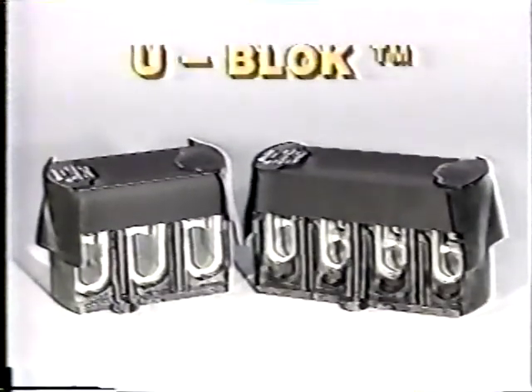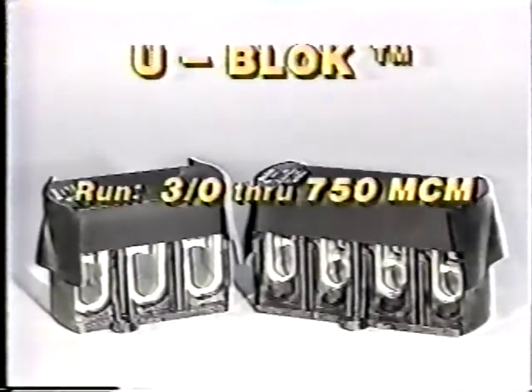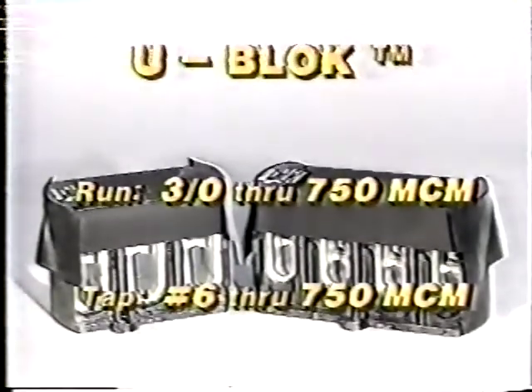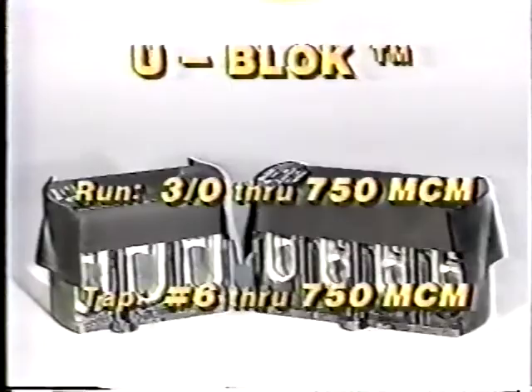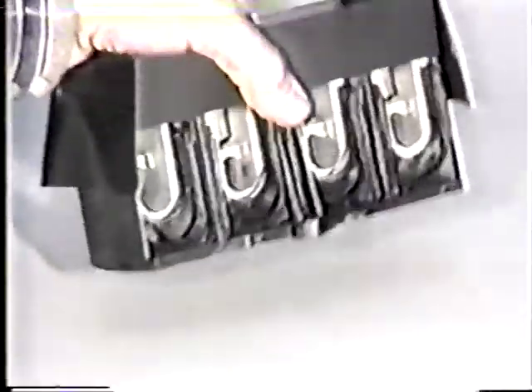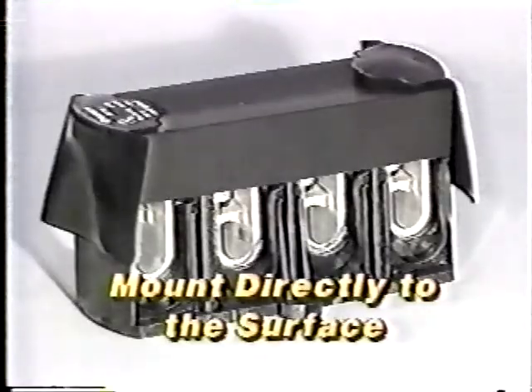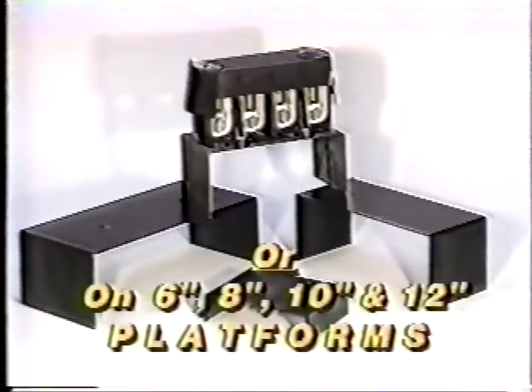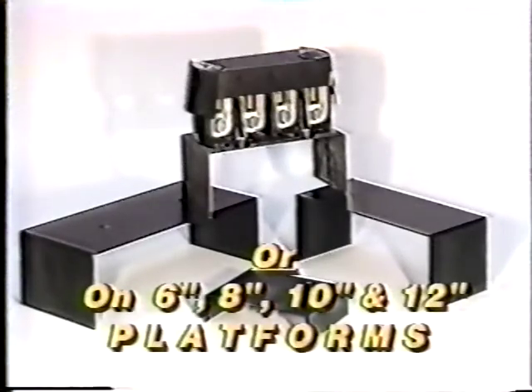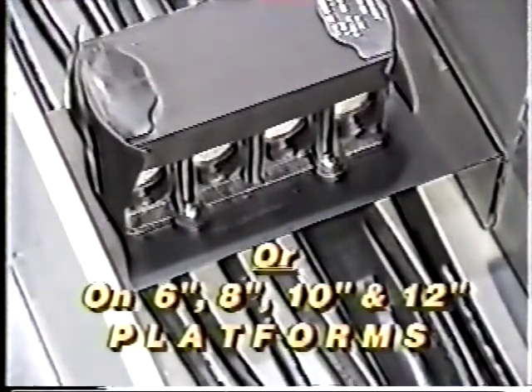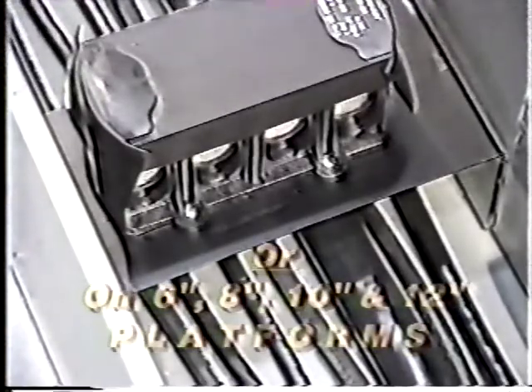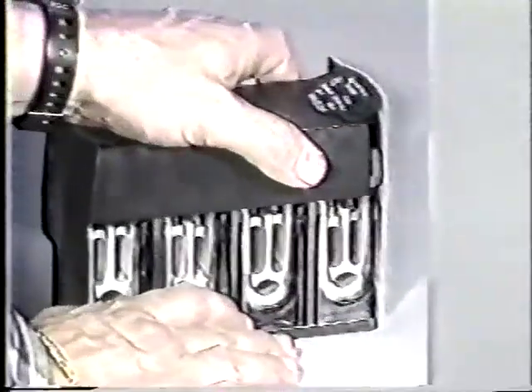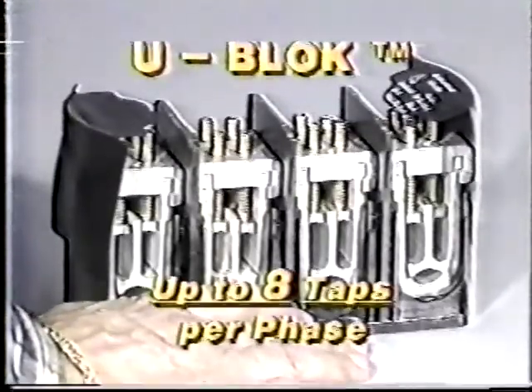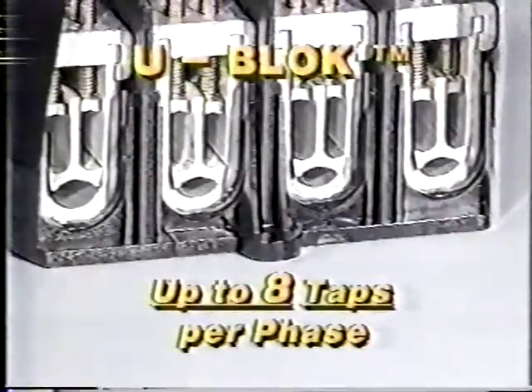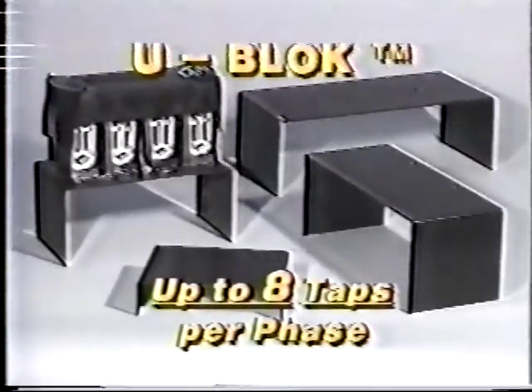Burndy's U-Bloks will accommodate run conductors ranging from 3/0 through 750 MCM. They'll also handle tap conductors from number 6 through 750 MCM. U-Bloks can be ordered to mount directly to the surface or with platforms for 6, 8, 10, and 12-inch gutters. With these platforms, through cables can pass under the connector, eliminating the need for termination. The FlexiTap system also includes U-Bloks which can handle up to 8 taps per phase. They too can be provided for direct mounting or with different mounting platforms.